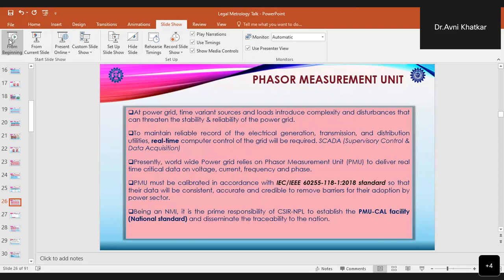So these PMUs must be calibrated in accordance with the latest standard, that is the IEEE/IEC 60255-118-1:2018 standard, so that the data which we get from these PMUs is consistent, accurate, and credible in order to remove all the barriers for their adoption by the power sector. And being an NMI, it is the prime responsibility of CSIR NPL to establish the phasor measurement unit calibration facility, which is a national standard, and to disseminate its traceability to the nation.